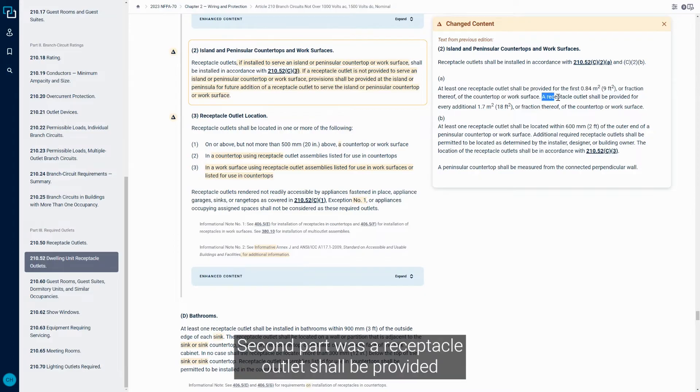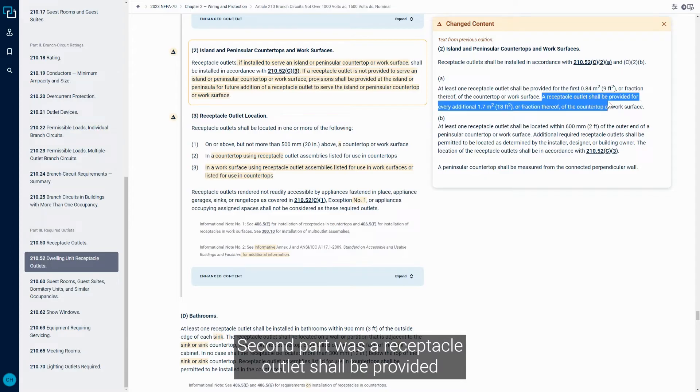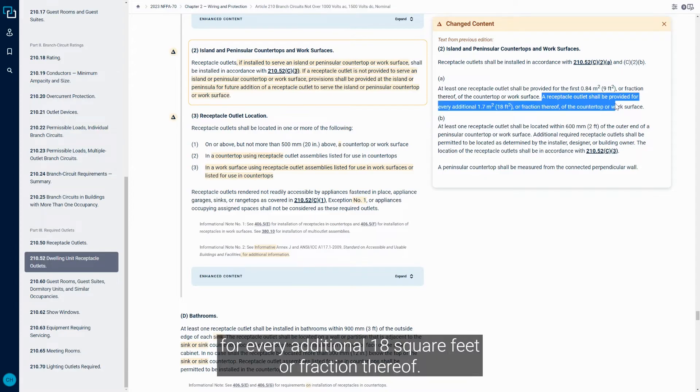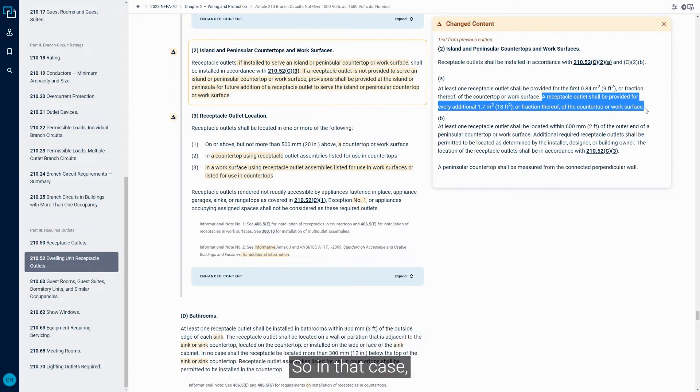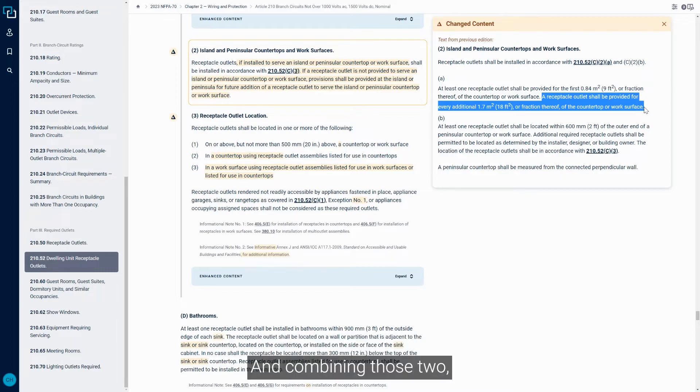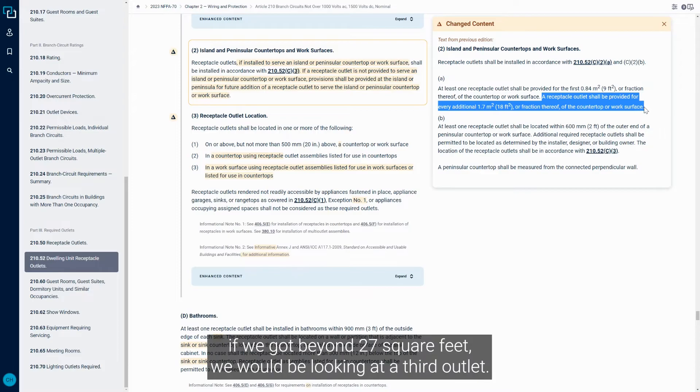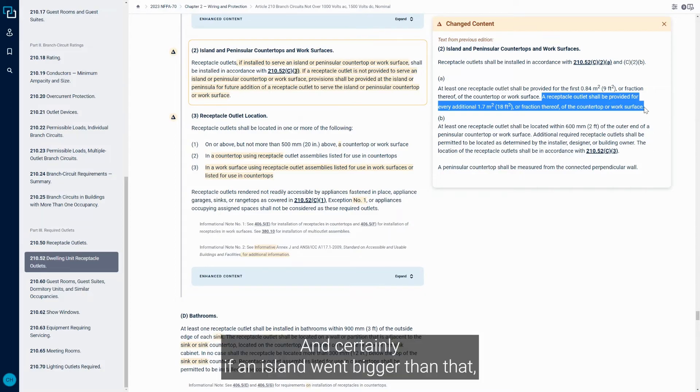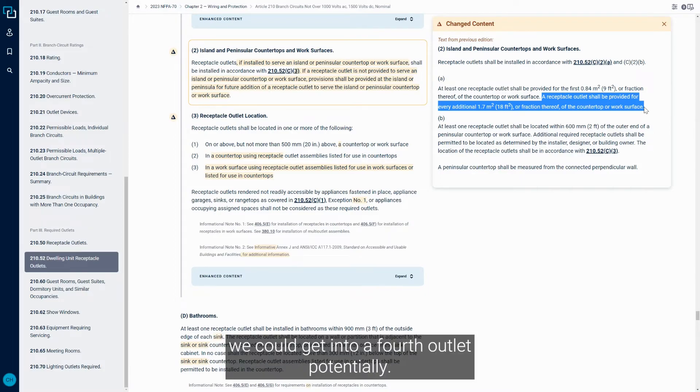Second part was a Receptacle Outlet shall be provided for every additional 18 square feet or fraction thereof. So in that case, if we got beyond the nine square feet, we would need a second outlet. And combining those two, if we got beyond 27 square feet, we would be looking at a third outlet. And certainly if an island went bigger than that, we could get into a fourth outlet potentially.